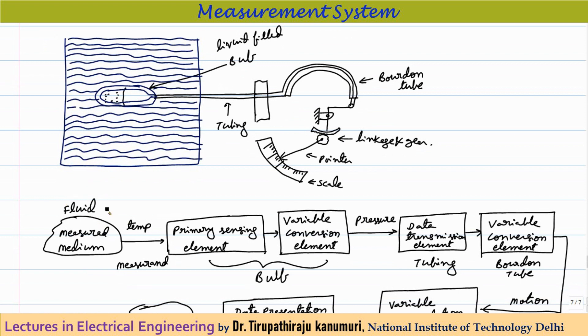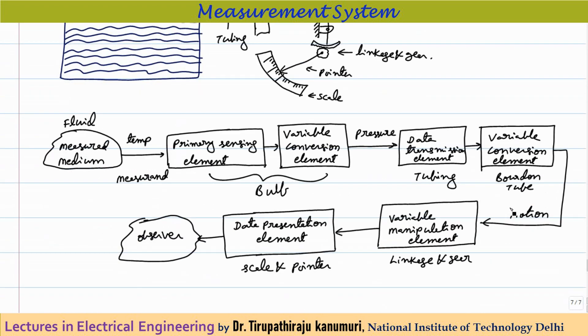Mapping this to functional blocks: the liquid bulb acts as the primary sensing element and variable conversion element, converting temperature into pressure. The tubing transmits the pressure. The Bourdon tube acts as another variable conversion element, converting pressure into linear motion. The linkage-gear mechanism acts as the variable manipulation element, amplifying the motion. Finally, the scale and pointer act as the data presentation element.